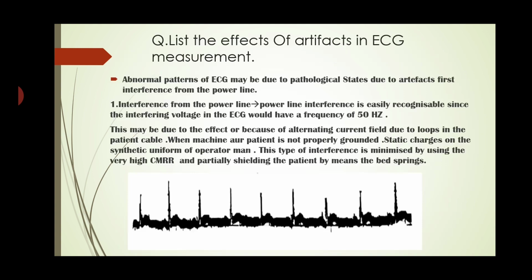Static charges on the synthetic uniform of the operator can also cause it. This type of interference is minimized by using a very high CMRR and partially shielding the patient by means of the bed springs. So by using this we can avoid this interference.